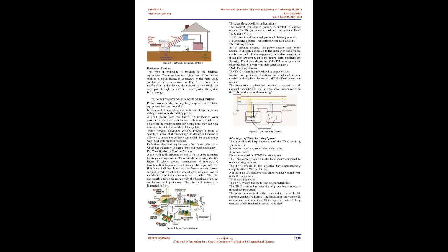TN earthing system. In TN earthing systems, the power source, transformer neutral, is directly connected to the earth with one or more conductors, and all the exposed conductive parts of an installation are connected to the neutral earth conductor or security. The three subsystems of the TN main system are described below, along with their salient features.